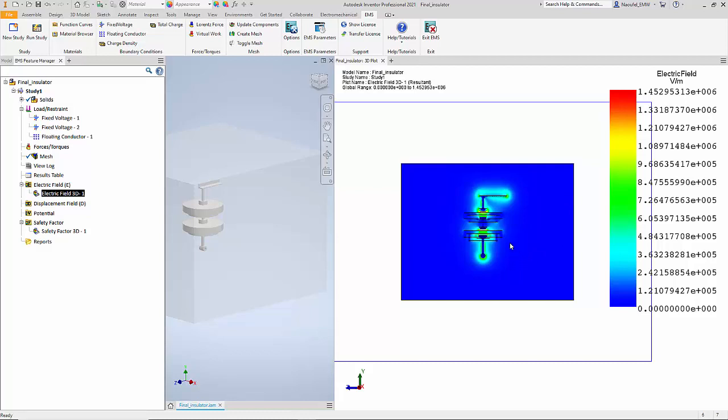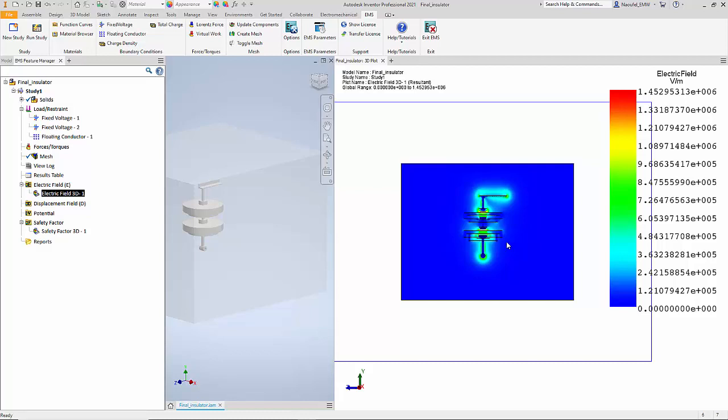Notice that the breakdown can occur not just in the insulator solid component but also in the air region surrounding these components. So it is important to be able to visualize the electric field distribution not just in the solid components but also in the air region surrounding them. This plot gives you a good idea of how the electric field is distributed in the air region.